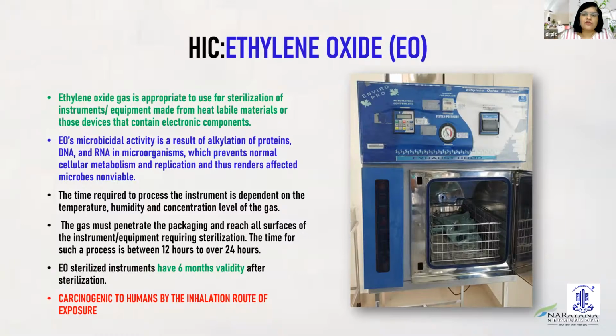At the same time, we have to remember the gases which come out from the ethylene oxide (ETO) sterilization need to be disposed of at a level higher than the hospital level. So that is very important. But at the same time, ethylene oxide is still regularly being used, and we should probably look in a direction where ethylene oxide can be substituted by something better.